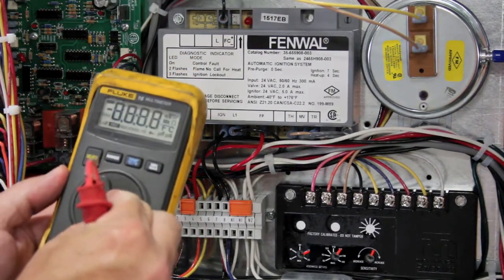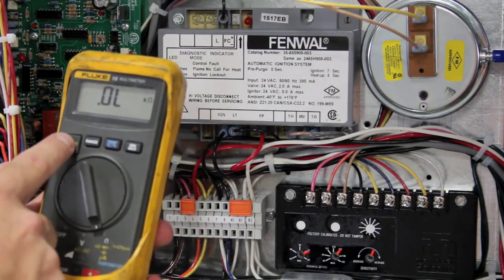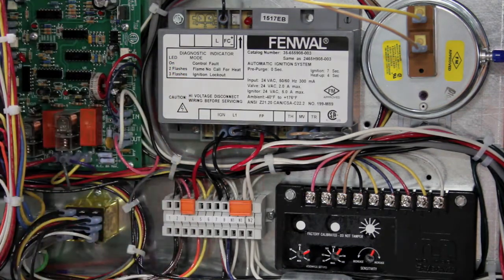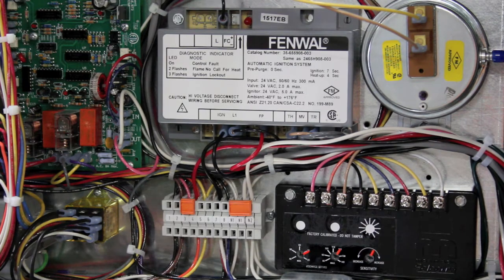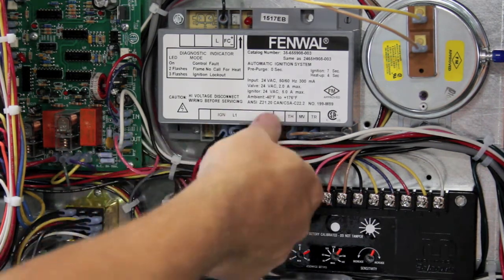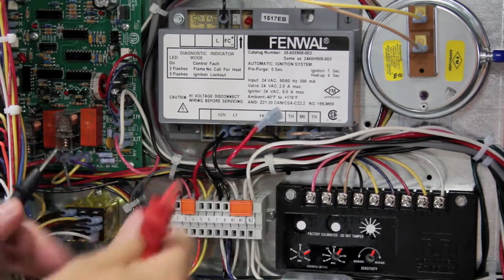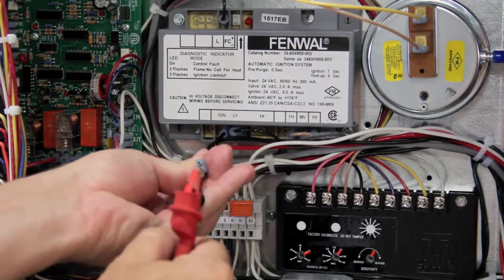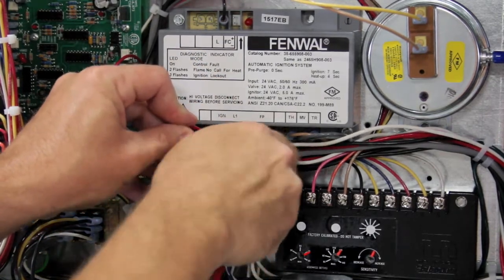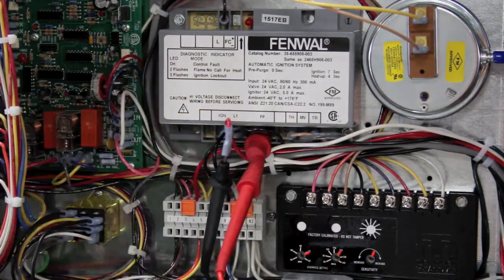Now connect your DC microamp meter to your flame safeguard. Verify your meter is on DC microamps. Remove the single red wire off the Fenwal flame safeguard relay — it will be marked FP. Take your black lead and attach to the push-on that was on the spade, and your red lead connect to the spade of the board.